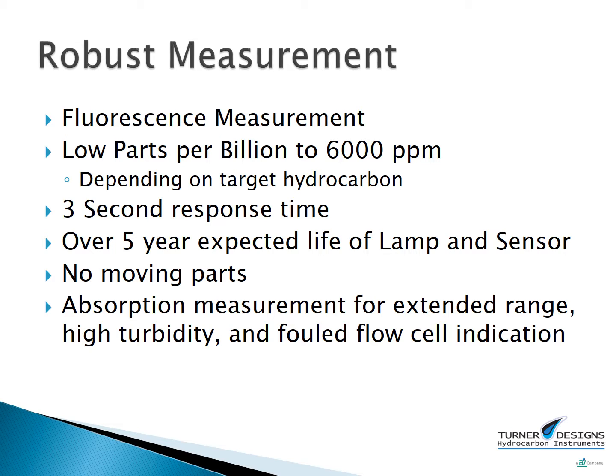For the robust measurement of hydrocarbons in water, the TD120 uses both fluorescence and absorption technologies. This achieves the indication of hydrocarbons in water from the low parts per billion up through about 6,000 parts per million, depending on the target hydrocarbon. Because the fluorescence response is immediate, and because the TD120 uses no chemicals, reagents, or other sample homogenization, the TD120 will respond to a step change in hydrocarbon concentration in about 3 seconds.